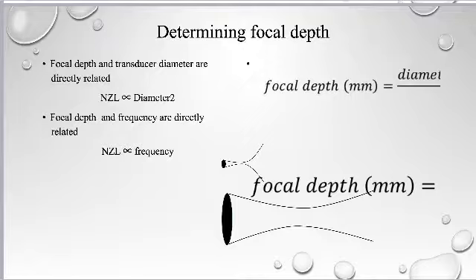All right, so very important, the focal depth and transducer diameter are directly related. The bigger your diameter, the deeper the focal depth. And it turns out it's related by its square. If I double my diameter, I increase my focal depth by a factor of 4. If I triple my diameter, I increase my focal depth by a factor of 9.